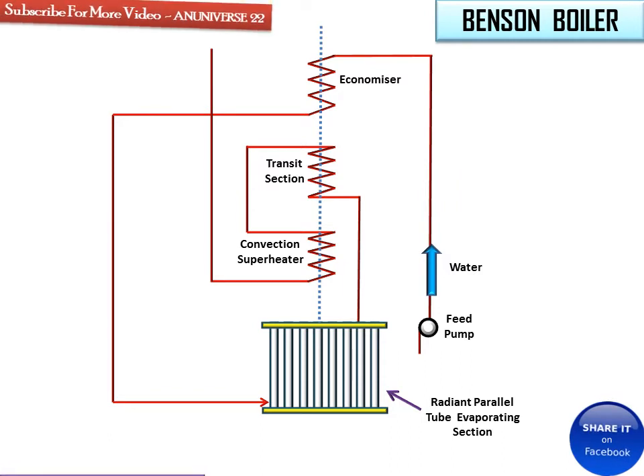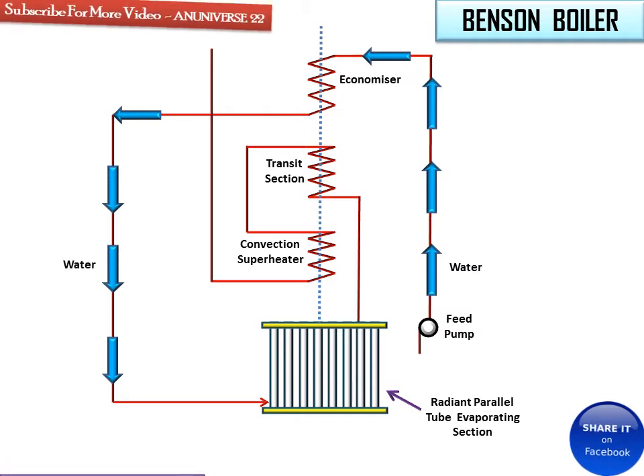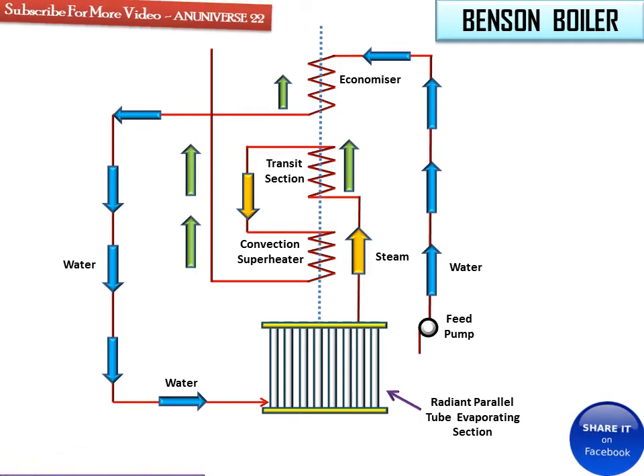With the help of arrows, we can see water flowing to the economizer. From the economizer, heated by flue gases, it is supplied to the radiant parallel tube evaporating section. From there, saturated steam is supplied to the transit section, and from the transit section this saturated steam is supplied to the superheater. The green arrows show the path of the flue gases, and steam is supplied to the prime mover.